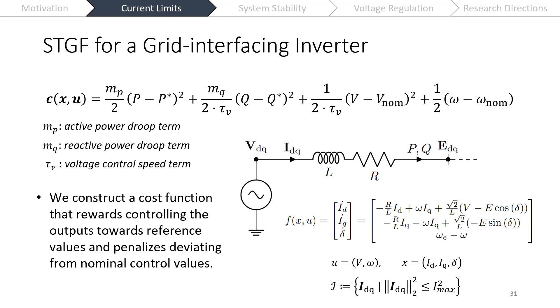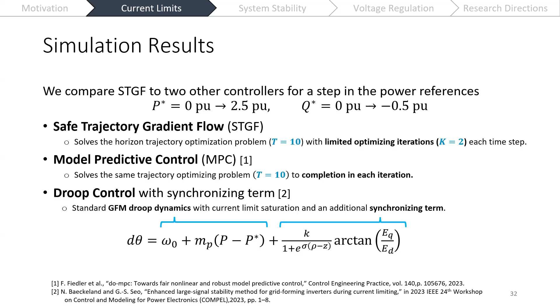We look at it here in simulations, comparing just for a step in these power references to see how the controller reacts. We're going to compare it to model predictive control, which is similar, but it's actually completely solving the optimal trajectory problem in each time step, while our safe trajectory gradient flow is only providing some limited optimizing iterations to update our trajectory. Then we're also going to be comparing to droop control here, which has an additional synchronizing term to make sure it actually remains stable and comes to some steady state point.